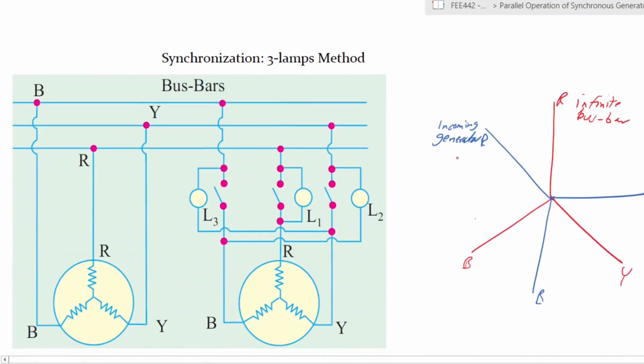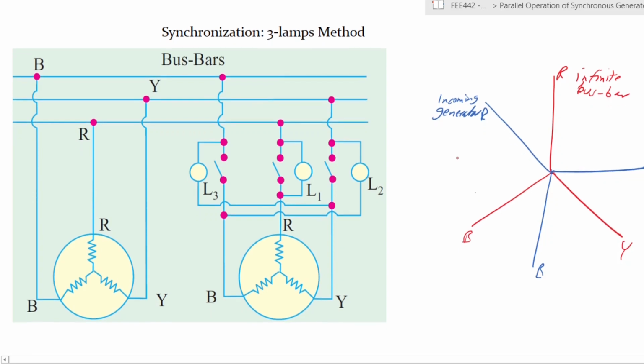So when you have synchronization, now we have a slightly different setup, still with 3 lamps, but you can see they have been set up slightly differently. This illustration shows the wiring for a setup which we want to connect to. So let's say this is our generator 1. Let's call this infinite bus bars, and it is part of a system that you want to connect to. And you want your generator 2 to connect to your system of infinite bus bars with your generator 1 already running, right?